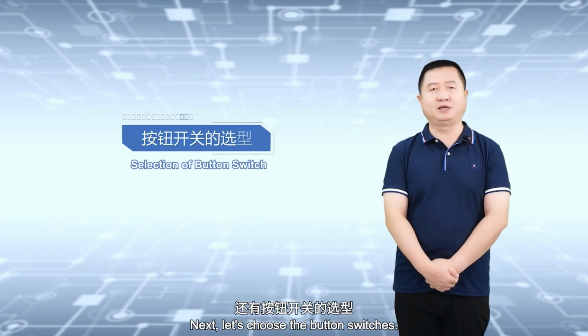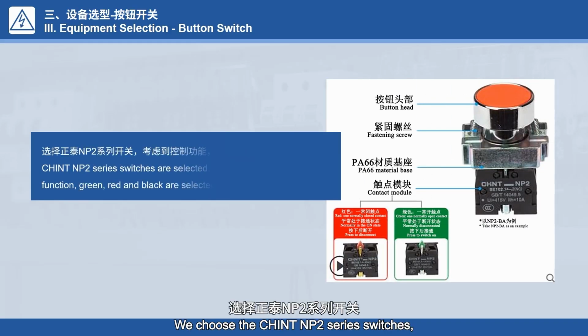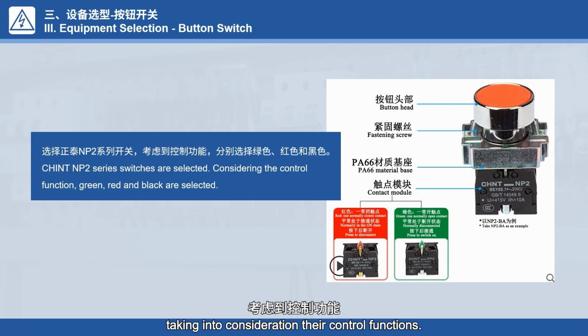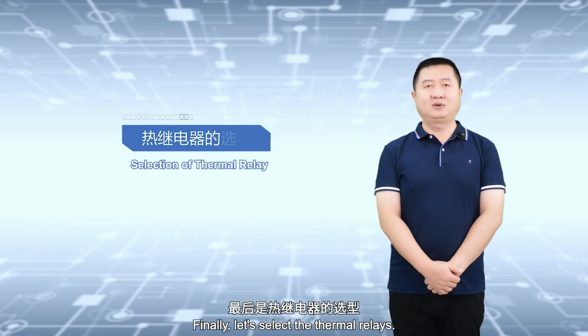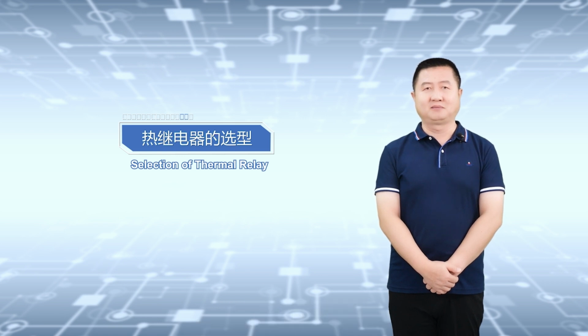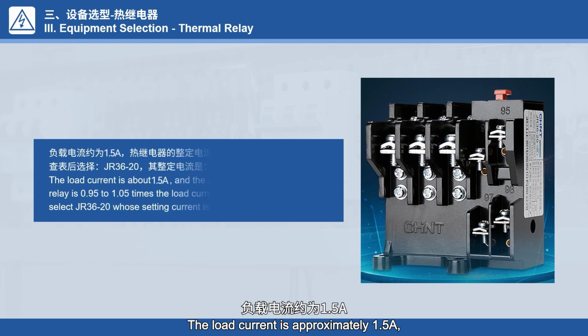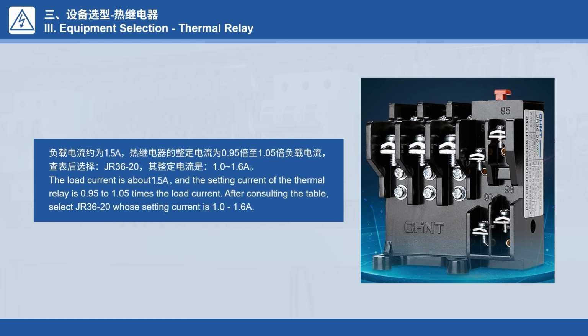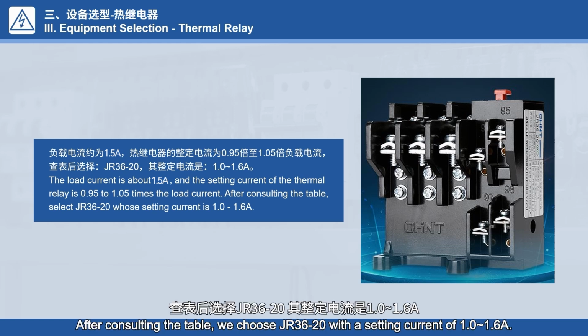Next, let's choose the button switches. We choose the Chint NP2 series switches, taking into consideration their control functions. We select green for the inching control button, black for the continuous control button, and red for the stop button. Finally, let's select the thermal relays. The load current is approximately 1.5 amperes, and the setting current of the thermal relay is 0.95 to 1.05 times the load current. After consulting the table, we choose JR36-20 with a setting current of 1 to 1.6 amperes.